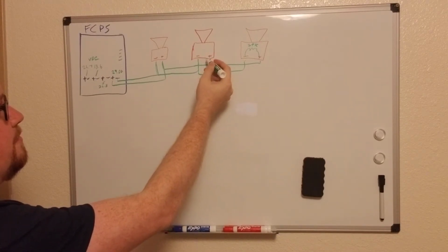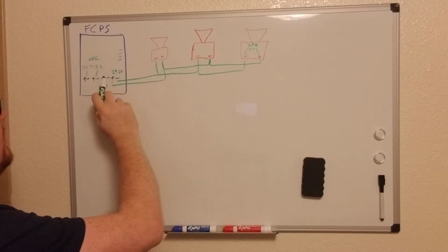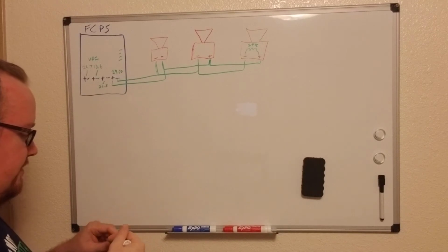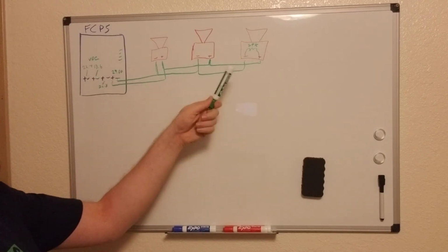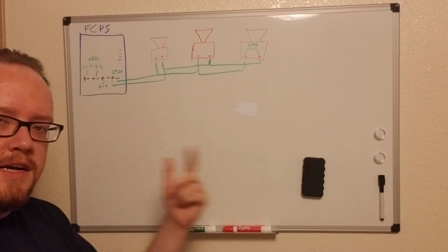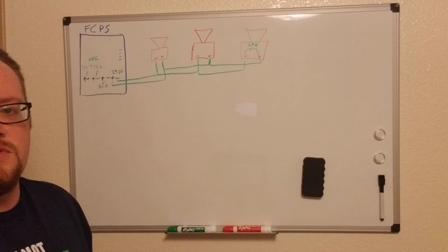Now, as soon as you fix the issue and you put your meter back on and you see this 29 went down to 26.8 or 27, then you know this is fixed. You do not have to go back to the panel and check and see if that trouble's gone. You know the trouble's already gone.